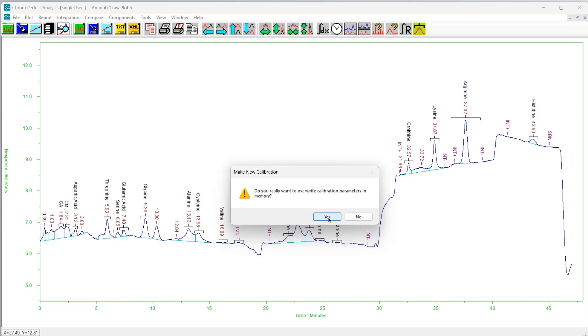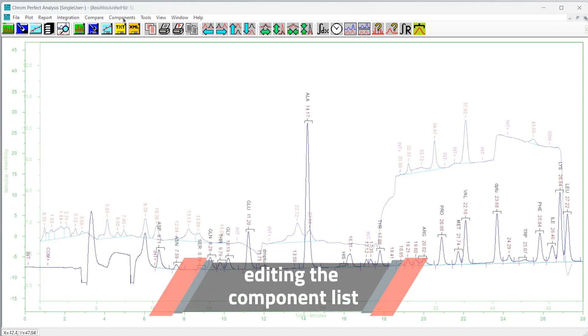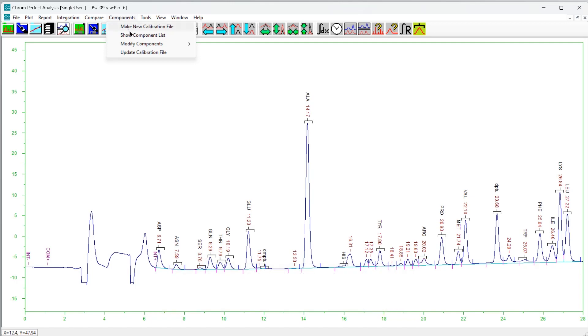To start with an empty calibration file, choose Components, then Make New Calibration File. You will be asked whether you wish to overwrite the calibration file in memory. If you press Yes, then all component information is deleted. Existing calibration and bound files are not altered until you specifically overwrite them. The remaining actions in this section may be applied to a new or an existing calibration file.